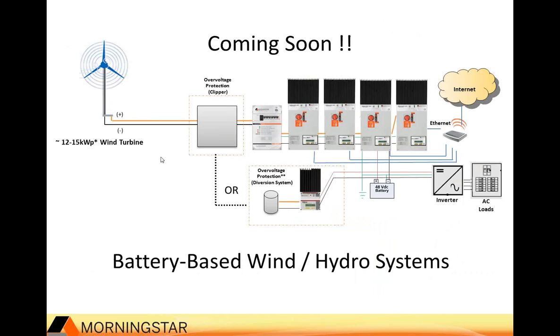And another feature coming along shortly is additional software that allows the paralleling of up to 4 controllers. These 4 controllers will communicate via Ethernet, and they would track and sweep the maximum power point as if they were one controller. So this isn't parallel battery charging, it's actually paralleling of the input of the controller. To a wind turbine or to a large PV array, this would appear as one extremely large charge controller. They would sweep and track as one device. This allows some new opportunities with large wind turbines or existing combined PV arrays that are already greater than 3.2 kilowatts. You can now go 12 to 15 kilowatts in size and be able to easily charge a 48 volt battery through this down conversion. So these two features, the DC transfer switch and the paralleling software, will be coming out in the coming months.